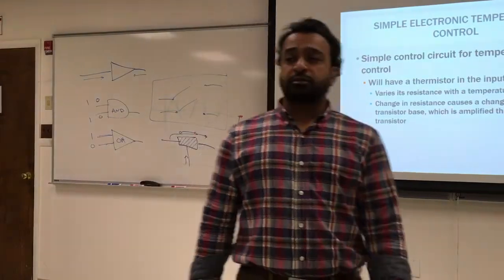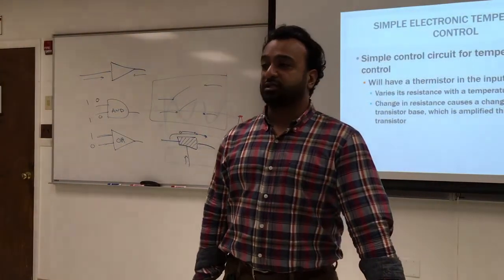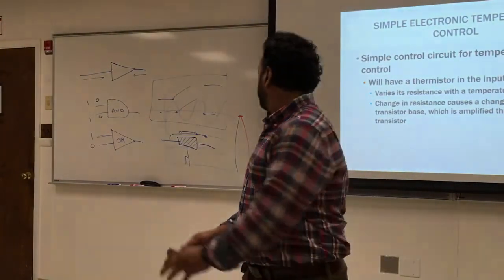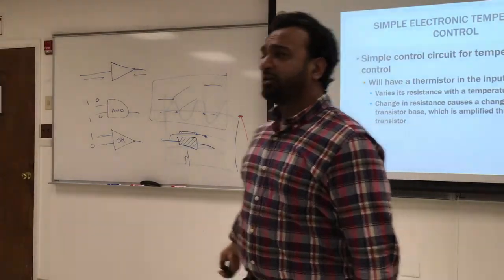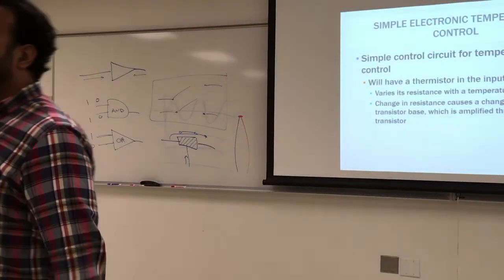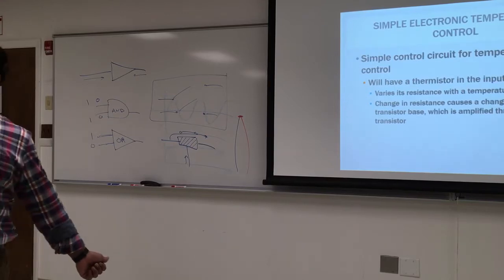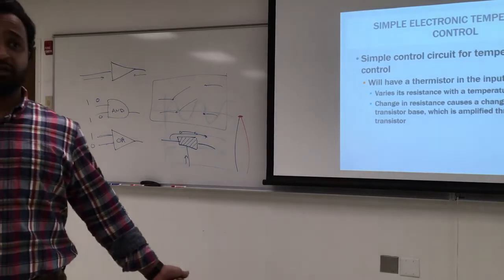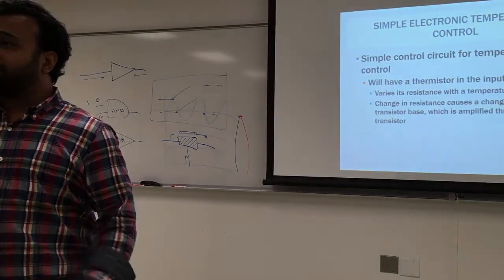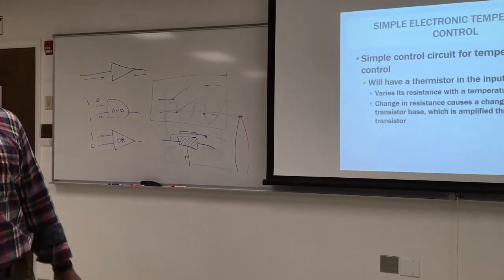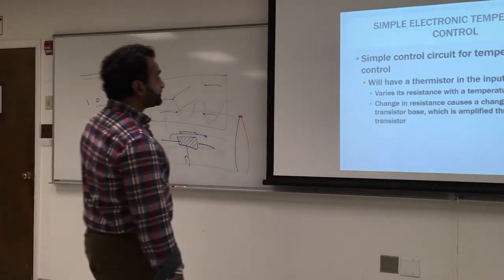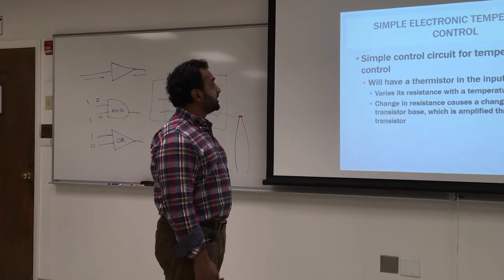And again, thermocouples change sensitivity. If you think of the device, what do you think will change the sensitivity and reaction time for those? Size of the wire, for example. How long is it exposed to the liquid? Is it submerged in water or is it just exposed in air? How fast is the air or fluid going through it? That will change its reaction time.